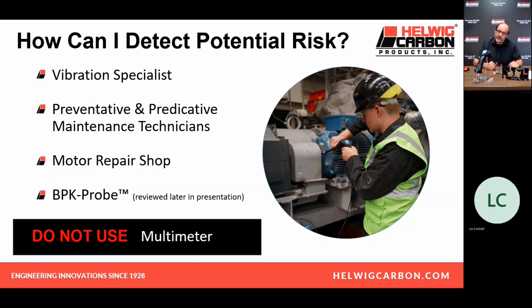Folks in motor shops are out on the floor. They take their very good Fluke or other very, very well-designed multimeter. They go against the shaft to ground, and it measures 0 ohms, and they go, we must be good. They put it on the voltage reading. They measure between the shaft and ground, no voltage, and they go, there, our motor is protected. It is exactly not true.